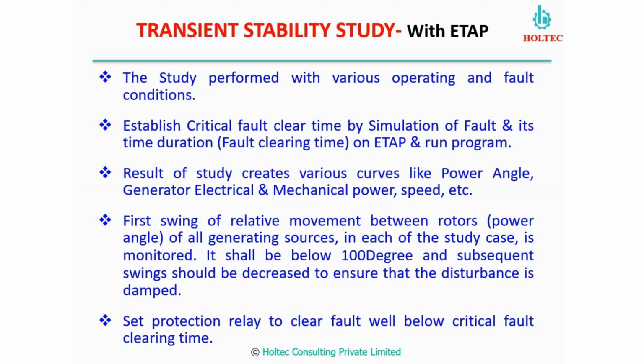So what results do we get? We get the results in terms of curves like power angle, generator electrical and mechanical power, speed, and voltage behavior during that fault condition and after it.